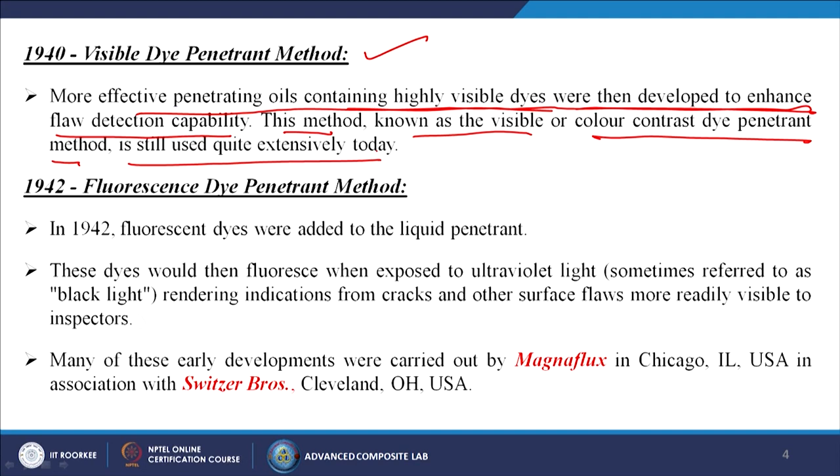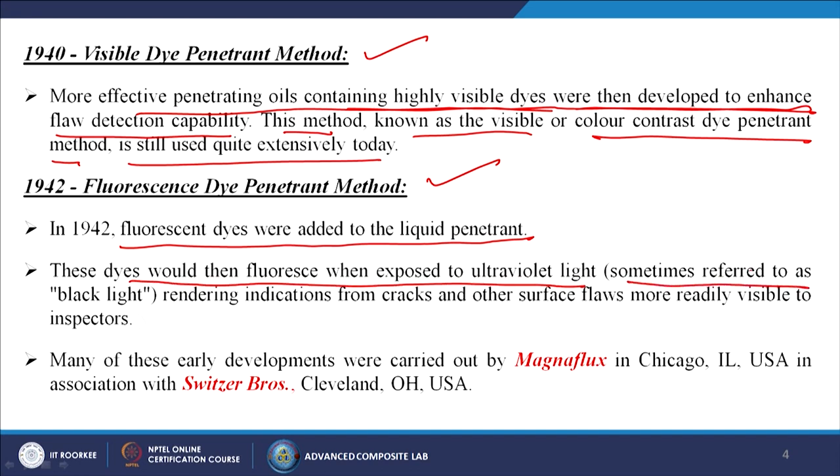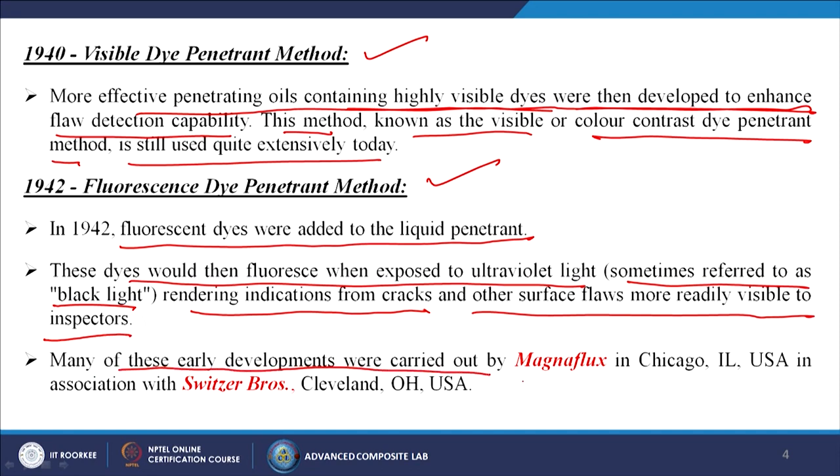In 1942, the fluorescent dye penetrant method was introduced. Fluorescent dyes were added to the liquid penetrant; these dyes fluoresce when exposed to ultraviolet light, sometimes referred to as black light, rendering indications from cracks and other surface flaws more readily visible to inspectors. Many of these early developments were carried out by Magnaflux in Chicago, Illinois, USA, in association with Switzer Brothers, Cleveland, Ohio, USA.